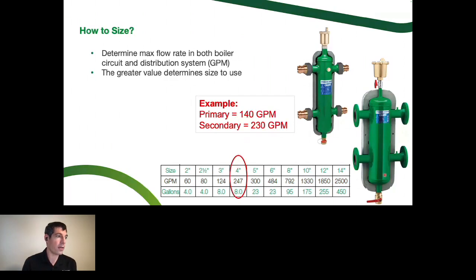You could buy a 14-inch separator and you would make me, a Caleffi employee, very happy, because that's going to be a very expensive tank. Actually, don't do that, because we only go up to 12-inch CRN separators in Canada. So don't buy a 14-inch, or you're not going to have the right listing. So let's say you buy that. It's going to be a very expensive buffer tank. You could probably buy a buffer tank that would have a much bigger capacity for less money at that point. The 12-inch is only required if you need an 1850 GPM flow rate.